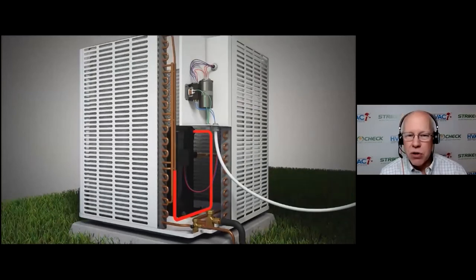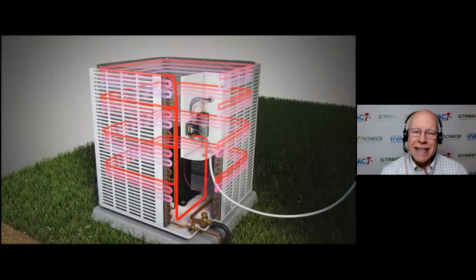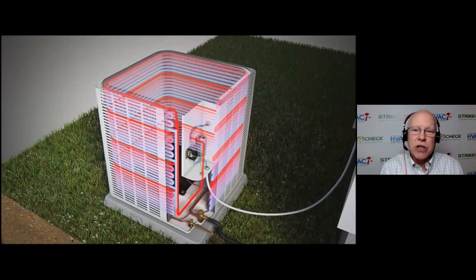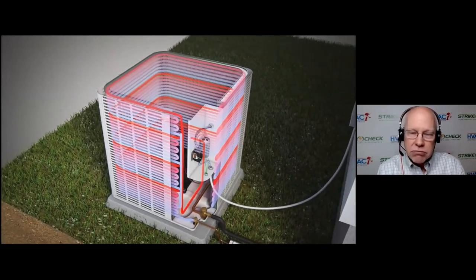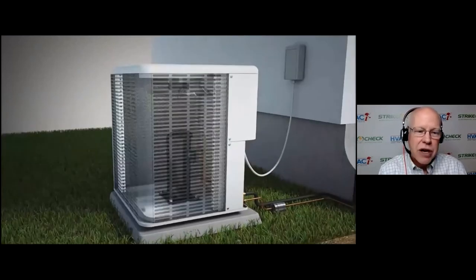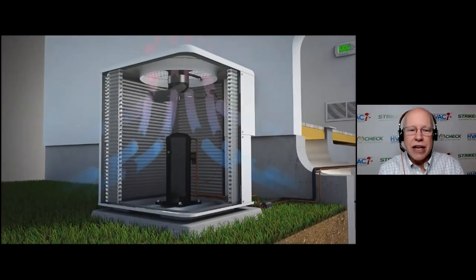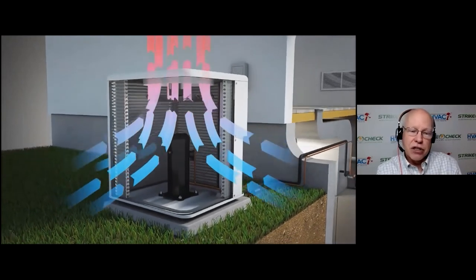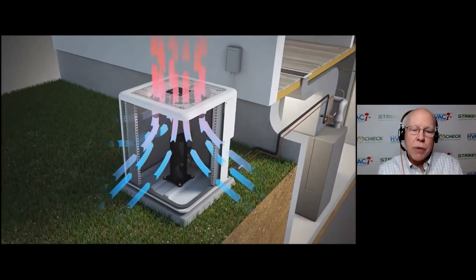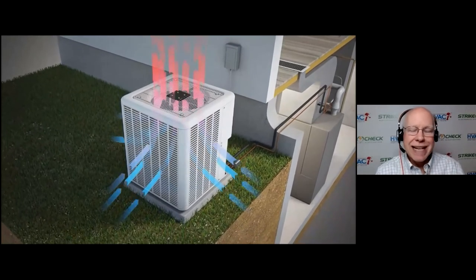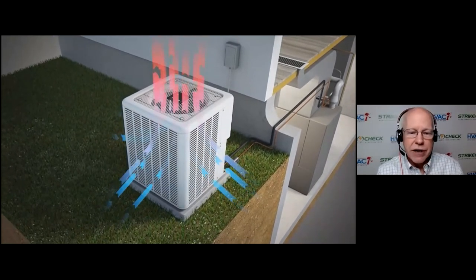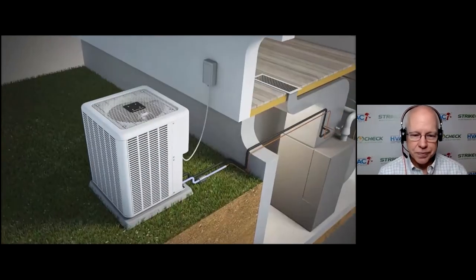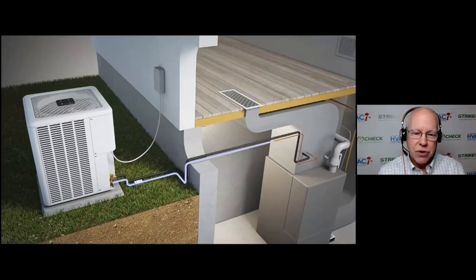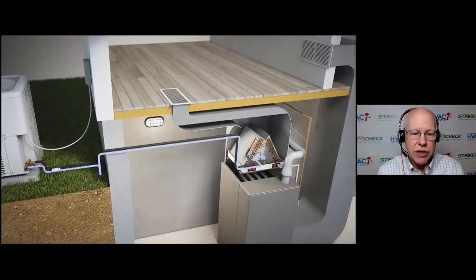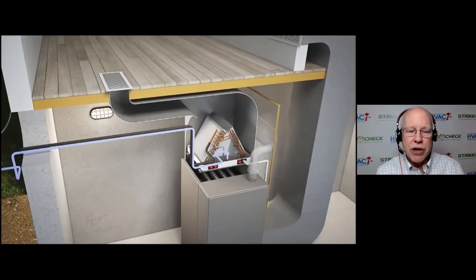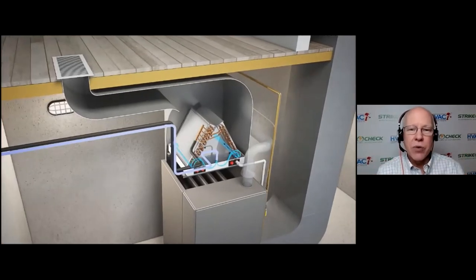So back and forth through all those coils. While that's happening, the fan engages and pulls ambient air through and across those coils. And lo and behold, the second law of thermodynamics takes over and the heat leaves the refrigerant and goes into the passing air, as shown here by the blue lines in and the warmer red lines coming out. The refrigerant changes back to a liquid, goes through that filter dryer, gets pumped inside by the compressor, goes through that expansion device or expansion valve, metering device, different people call it different things. And now it's going into the evaporator coil as a cold liquid refrigerant.